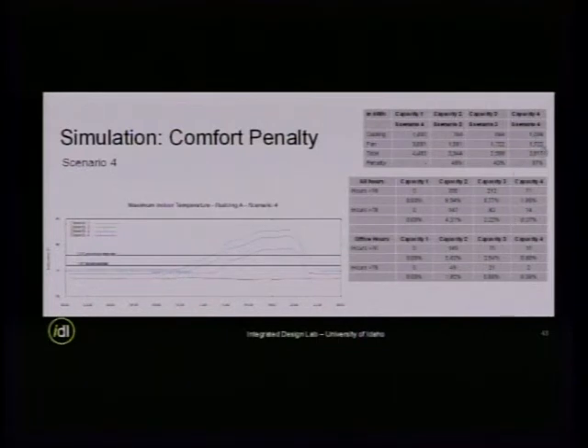This is the savings in terms of kilowatt hours that you will have for every scenario, and this is the potential. If you consider all hours, capacity four has 14 hours throughout the whole cooling season where it exceeds 78 degrees in the room. And if you consider only office hours from 9 to 5, it's only 2 hours.